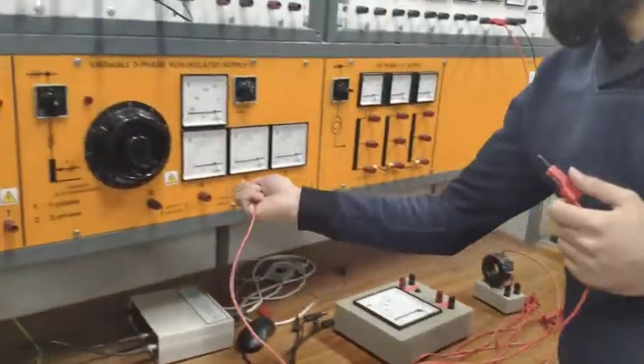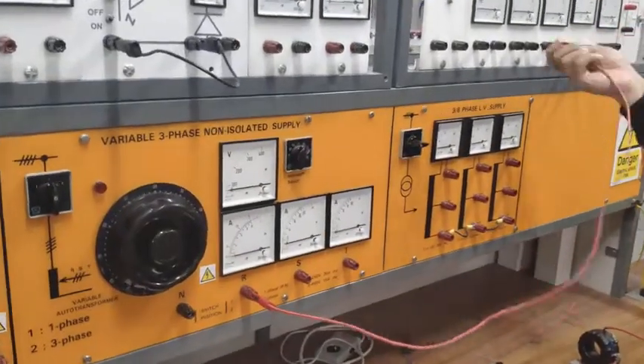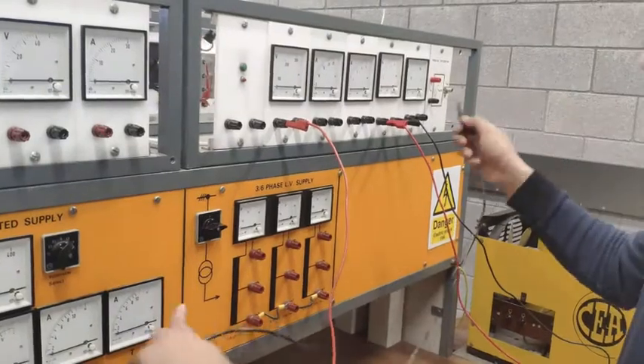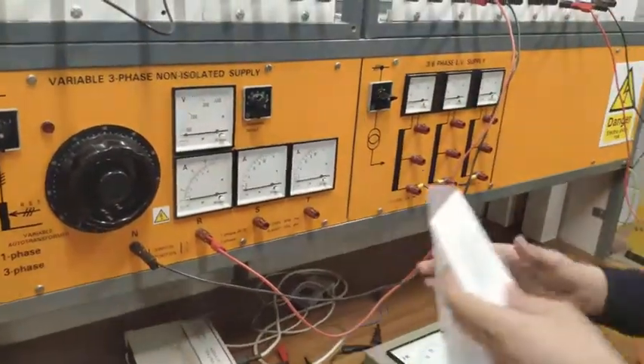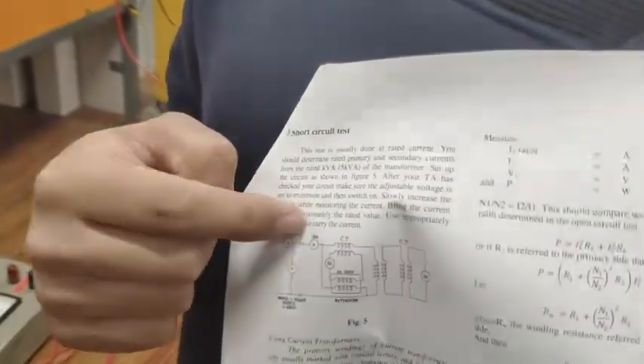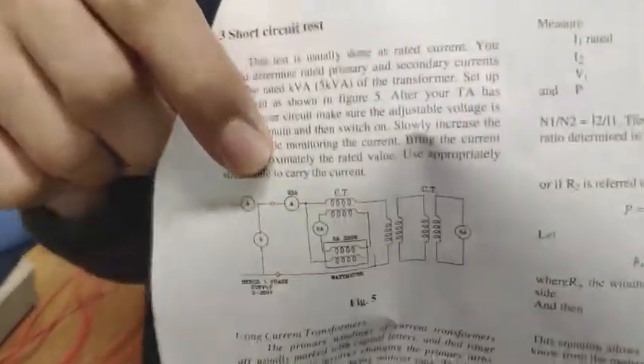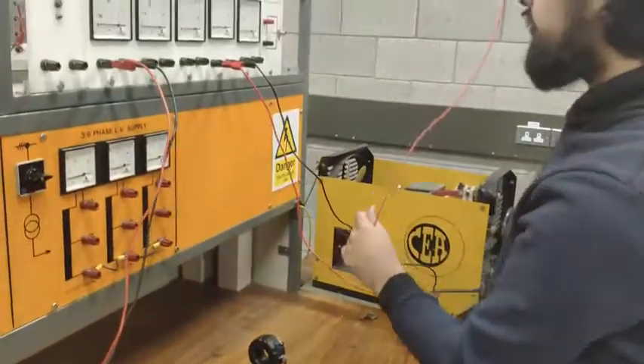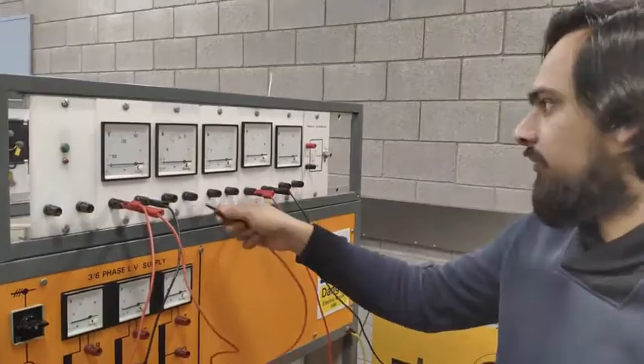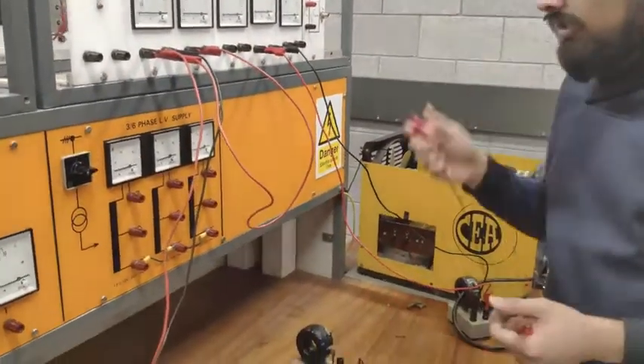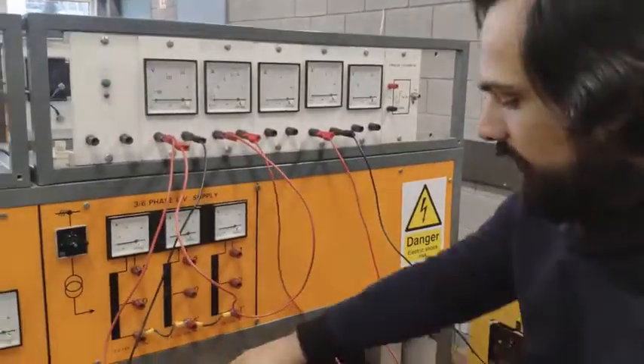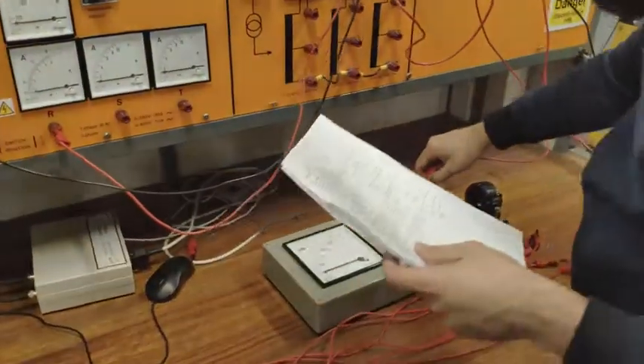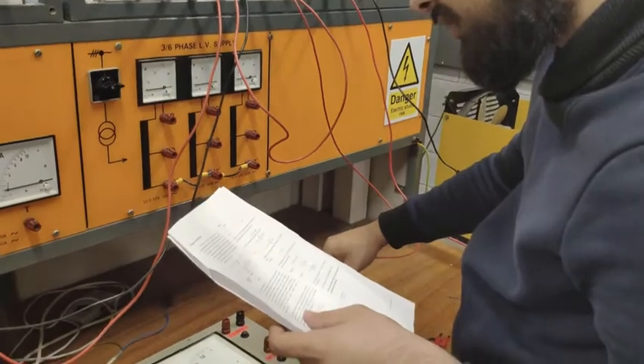Now we have to move on to the primary part. For the primary part, we always start from R phase. Then we move to the voltmeter. If you look at the circuit, coming out of the voltmeter you have an ammeter that's rated 25 amps. So I will connect it to 25 amps, and this is my 25 amp meter. And then in the circuit, when I come out of the 25 amps, I have to go to the CT.